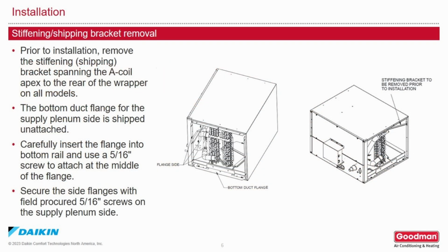The cased coils are shipped from the factory with a stiffening or a shipping bracket attached to the back side of the coil case that must be removed before installation. The bottom duct flange for the supply plenum is shipped unattached. Carefully insert the flange into the bottom rail and use a 5/16 screw to attach it at the middle of the flange. Secure the side flanges with field-supplied 5/16 screws on the supply plenum side.